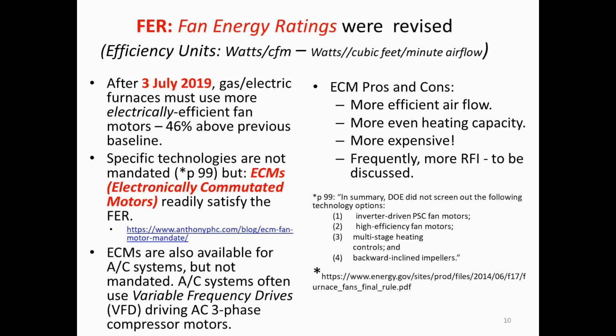The efficiency units are in watts per cubic foot per minute of airflow. That's what watts per CFM stands for. And so specific technologies weren't really mandated, but if you look at the footnote in the lower right-hand corner, the Department of Energy did not screen out, was the way they phrased it, the following 4 technology options: inverter-driven PSC fan motors, which I'm going to talk about, high-efficiency fan motors, which I'm also going to talk about, multi-stage heating controls, that will come up, and backward-inclined impellers. I have no idea what that means.